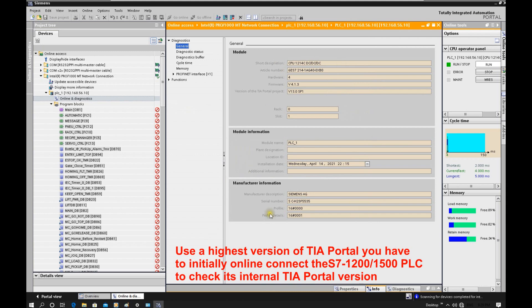We can double-click online and diagnostics. From here we can check the current firmware version and which TIA Portal software version programmed this CPU. This CPU was programmed with version 13, and the current firmware is version 4.1. That means we have to use version 13 software to upload this CPU. After the upload, we will upgrade this CPU firmware from version 4.1 to version 4.4.